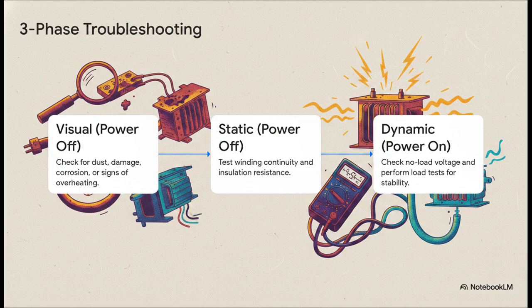First, with the power completely off, you do a full visual inspection. Is there dust? Any cracks? Any burn marks? Then, still with the power off, you do your static tests with meters to make sure it's electrically sound. Only after it passes those checks do you ever power it on for the live, dynamic tests.